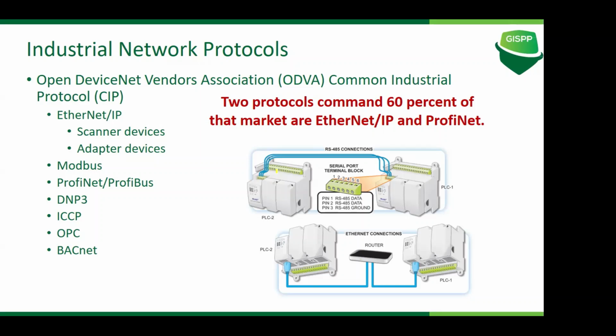It can connect up to 254 devices together in a certain industrial control network. It is widely used by distributed control systems, DCS, and the SCADAs that they use to interact between RTUs and DCS. Like I said before, RTUs are talking to DCS, and the DCS are now connected with SCADA main servers. So Modbus is the main protocol where RTU is talking to DCS, and now that DCS is talking to SCADA. Because if there is a conversion in between, availability will be impacted.